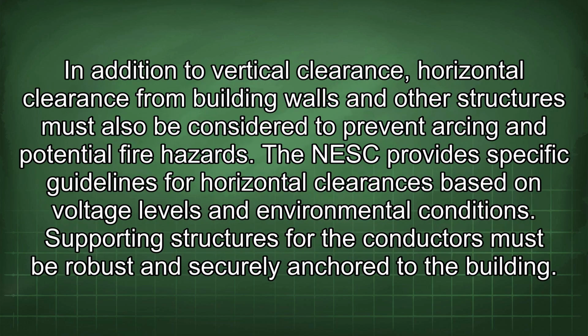In addition to vertical clearance, horizontal clearance from building walls and other structures must also be considered to prevent arcing and potential fire hazards. The NESC provides specific guidelines for horizontal clearances based on voltage levels and environmental conditions. Supporting structures for the conductors must be robust and securely anchored to the building.